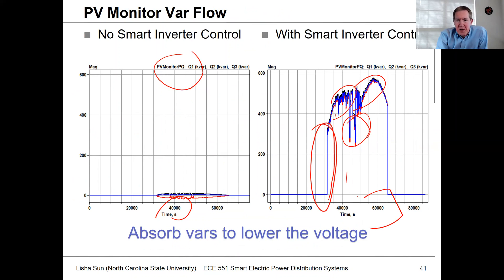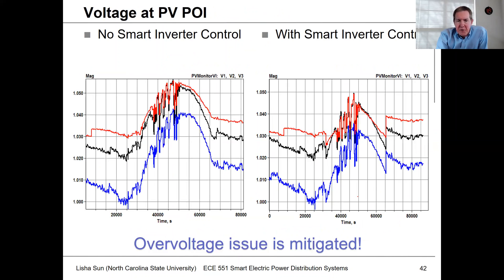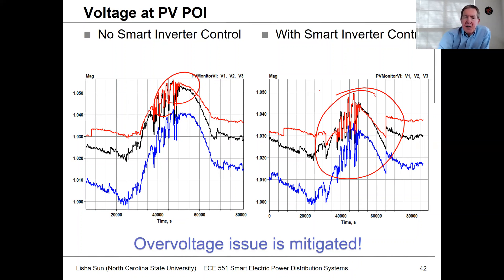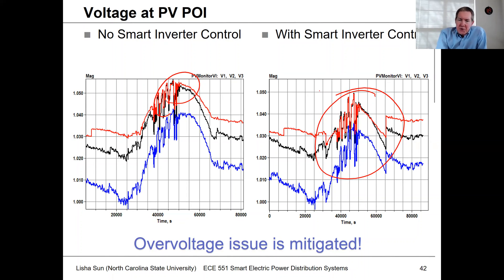That's what we see for the smart inverter control. Looking at the impact at the point of interconnection, you can see that initially with no smart inverter control, voltages would go rather high. When we have smart inverter control on, by absorbing vars, it basically pulls the voltage back down again — this is how it mitigates the overvoltage.